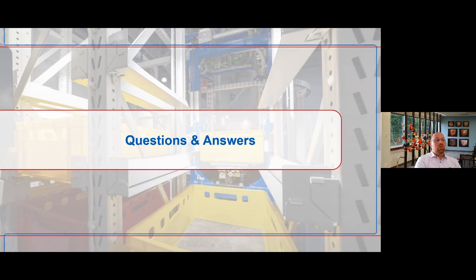And I think you mentioned that in those flow through or pushback type racks, where the pallets essentially butt up against one another, that forces the elimination of that longitudinal flue. The questioner says, in this instance, my view is that the longitudinal flue should be protected along the same design criteria as the face sprinklers, i.e. intersections of the longitudinal and transverse flues. And he's wondering if we have a view on this. A long question. Yeah, no, it is.